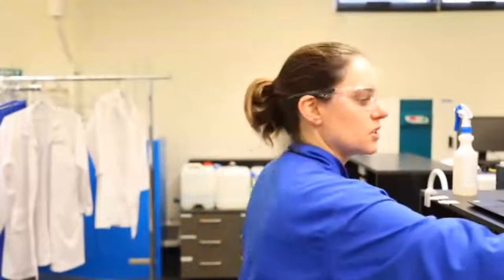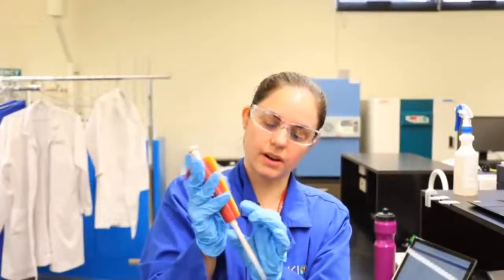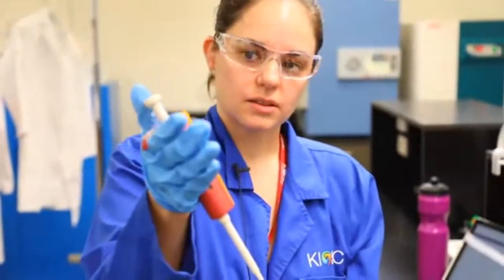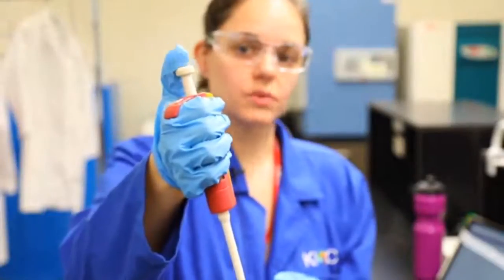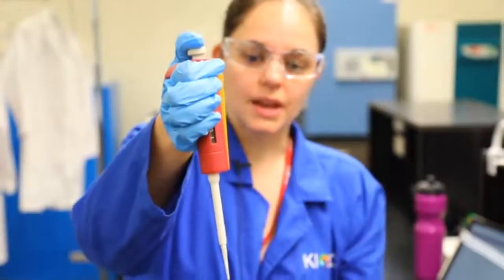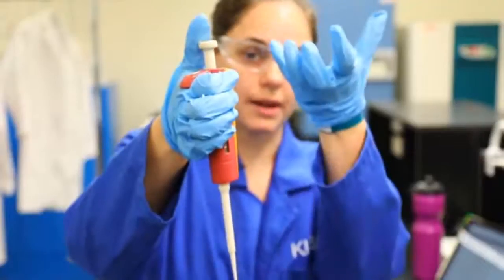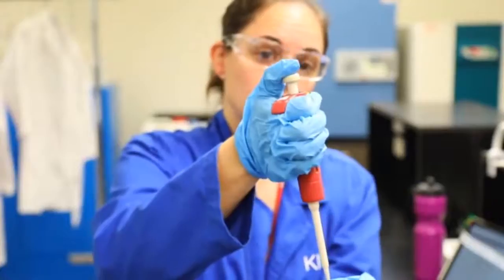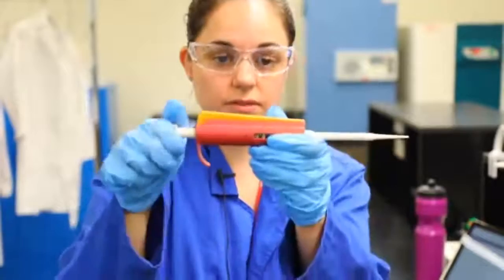Perfect. So I'm going to show you this one here. And this one is a 0.5 to 10 microliter. And the first thing you need to find is this knob at the top here. And you've got to find what is called the first stop, which is here. And that pushes out all the air out of the barrel. And that allows you, once you need to go and collect your liquid, to draw it all up. Once you've got your liquid, you then put it into the container that you want to inject in, and you push it all the way down to the bottom, which is your second stop. The other important thing is setting on the front here.